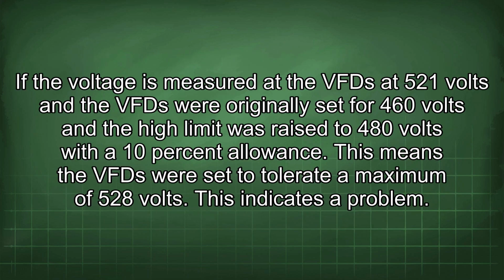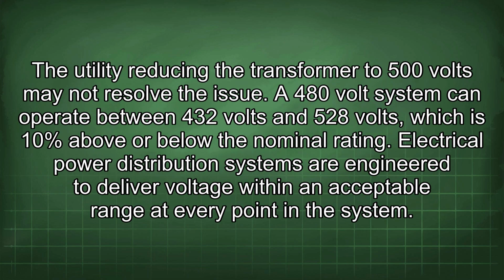If the voltage is measured at the VFD at 521 volts and the VFD were originally set for 460 volts and the high limit was raised to 480 volts with a 10% allowance, this means the VFD were set to tolerate a maximum of 528 volts. This indicates a problem. The utility reducing the transformer to 500 volts may not resolve the issue. A 480-volt system can operate between 432 volts and 528 volts, which is 10% above or below the nominal rating.